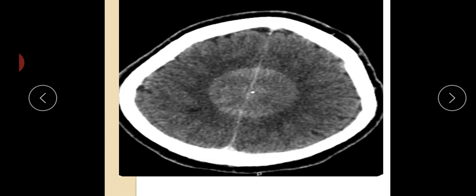This is an example of ring artifact, where a ring can be seen here. If a detector is miscalibrated, it will record incorrect data in every position or every projection. This misinformation is reconstructed as a ring in the image, with the radius of the ring determined by the position of the faulty detector in the detector array. Faulty detectors in rotate fixed units also record false information.